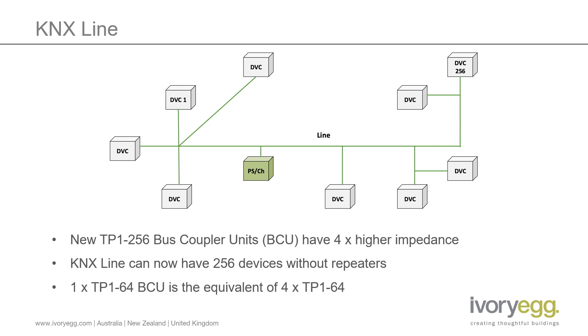The KNX standard was updated quite a few years ago with a new electronics design for bus coupler units — that's the electronics that connect a KNX device to the bus. Called TP1256, devices using this new standard have four times higher impedance than the original KNX devices, meaning they have a reduced data load on the bus.